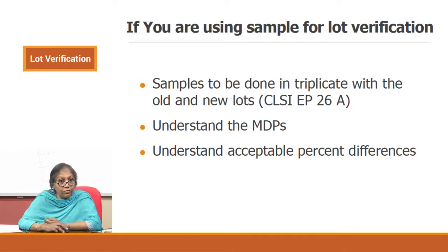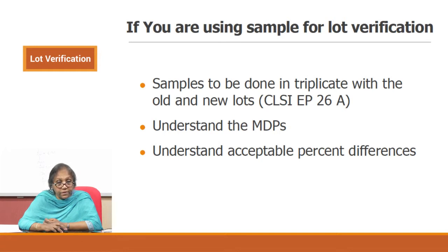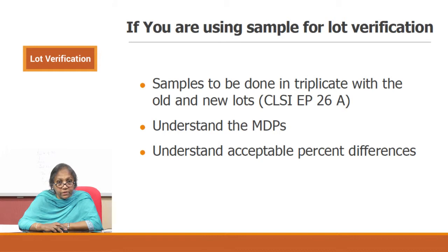If you are using samples for lot verification, samples are to be done in triplicate — ideally with the old and new lots — and you need to understand the medical decision points and the acceptable percentage differences. In QC soft there are tools for both mechanisms: both using sample and using the quality control.